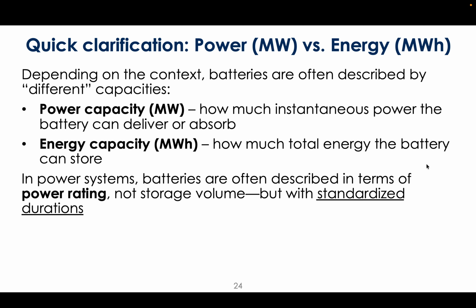That's the standard duration; otherwise they'll specify, like 100 megawatts for a 2 hour battery. So if I have 100 megawatts for a 4 hour battery, that means I can fully discharge it at rated power capacity for 4 hours, giving an energy capacity of 400 megawatt hours—just multiply by 4. Or I could run it at half capacity for 8 hours, but the energy capacity would still be 400 megawatt hours.